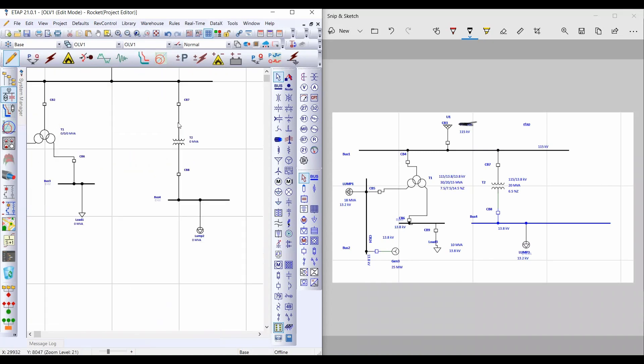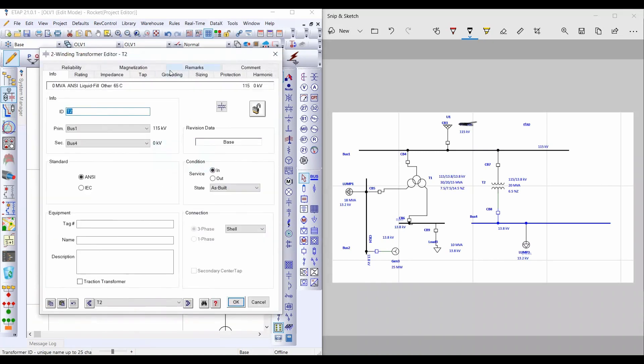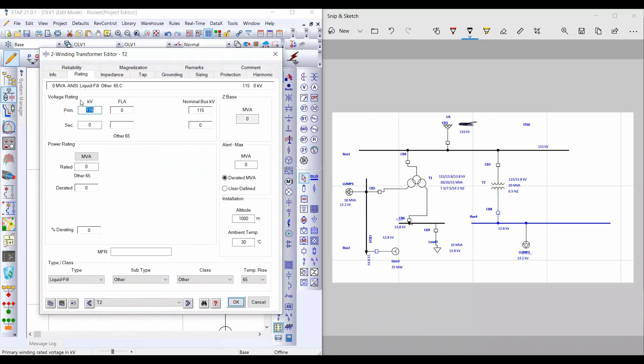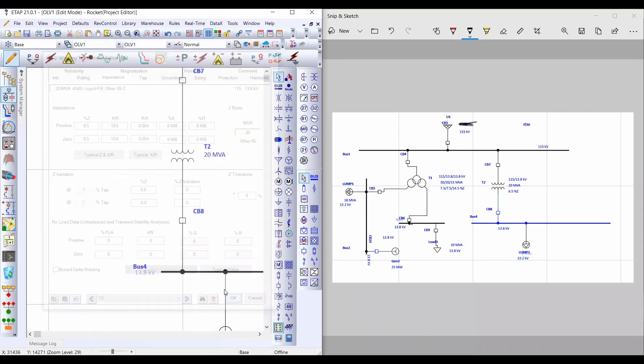Then I will insert data for the two-winding transformer. From Rating, the primary kilovolt is 115 and the secondary is 13.8 kV, and the MVA rating of this transformer is 20 MVA. From Impedance, select Typical Z and X/R ratio.